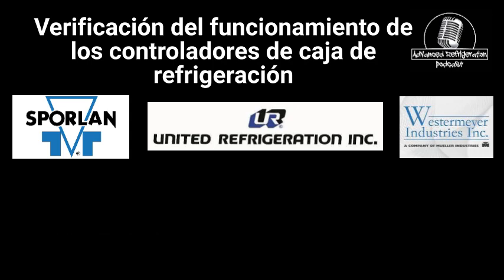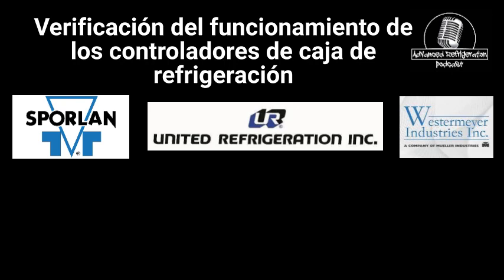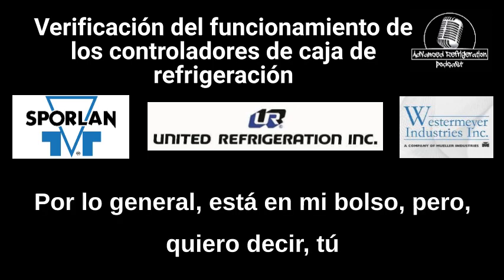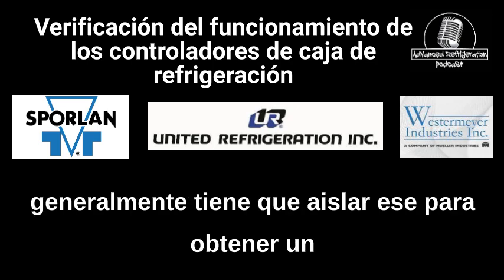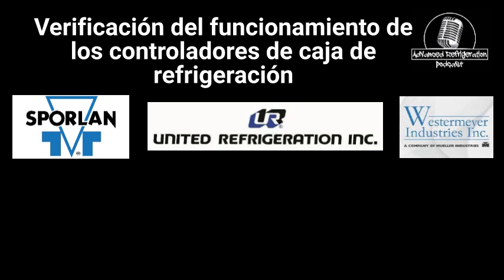Now, what I've been using for verifying them is either my Cooper, a Testo probe, and a Sporlan probe. The Sporlan probe is generally my go-to. It's usually in my bag. But you generally have to insulate that one to get a real good contact if you're checking sensors against it. Yeah.